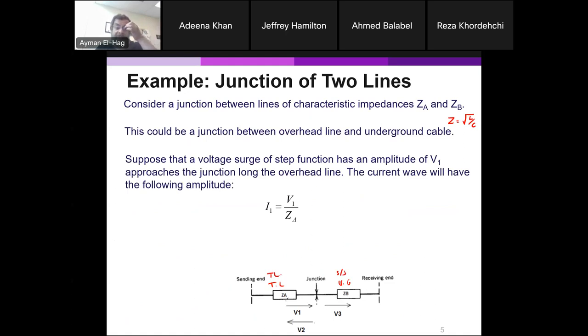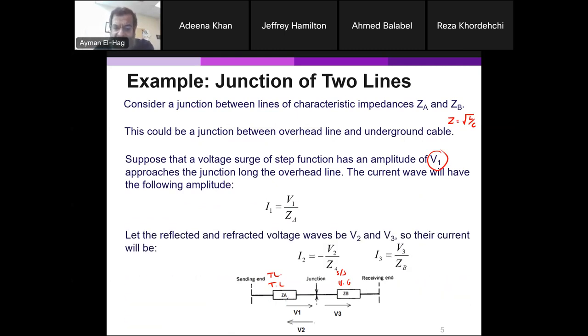Now, suppose we have a voltage surge. This could be lightning, let's say, or a switching event that happens somewhere in the overhead lines, and it has a magnitude of V1. We want to see what will happen to this V1, which is now approaching this junction. As we have a voltage waveform here, we'll have a current I1. So V1 divided by the characteristic impedance of the overhead lines will give me the surge current.